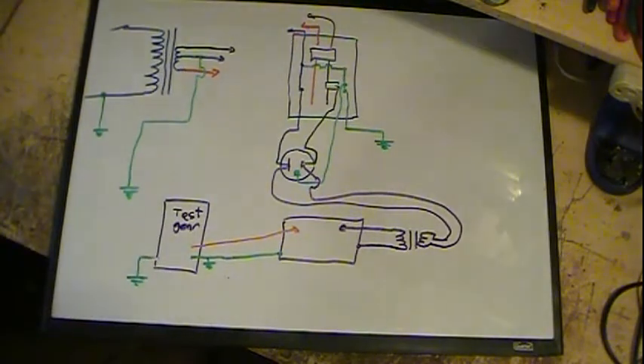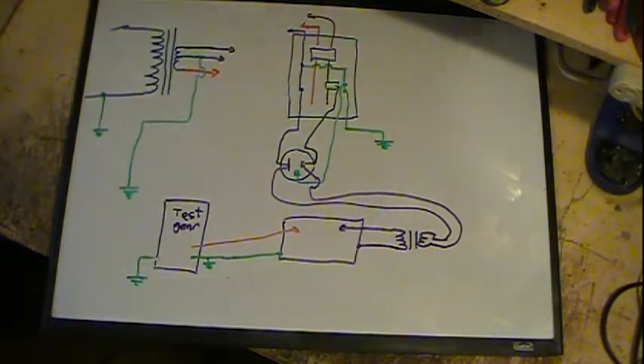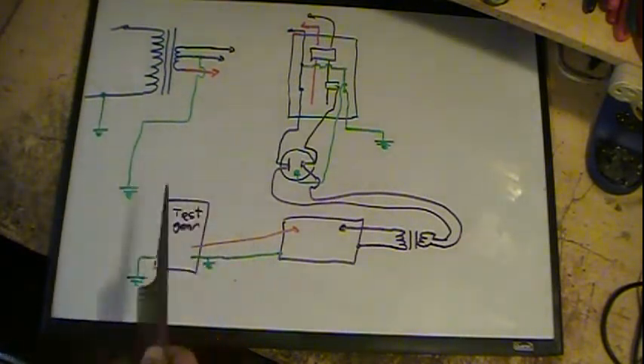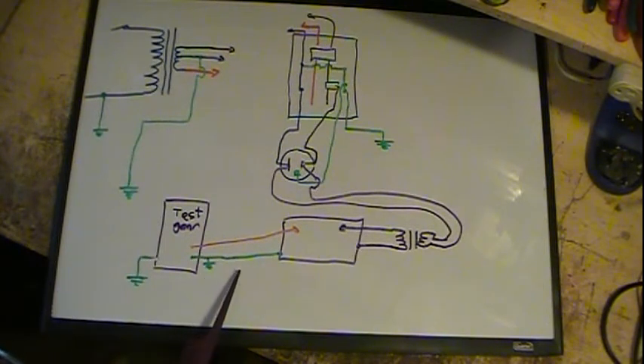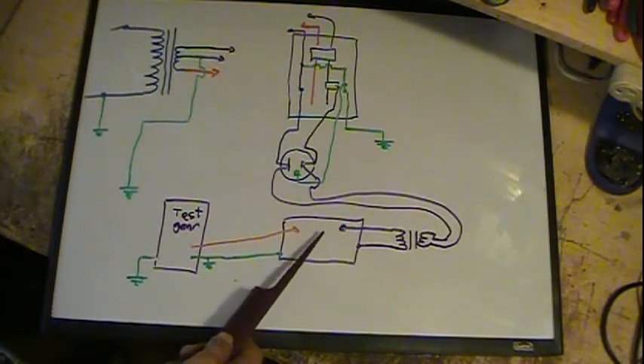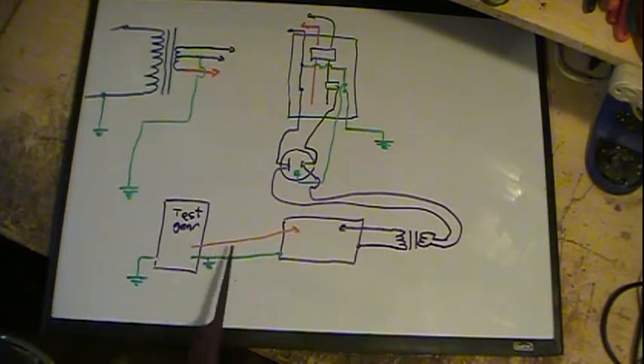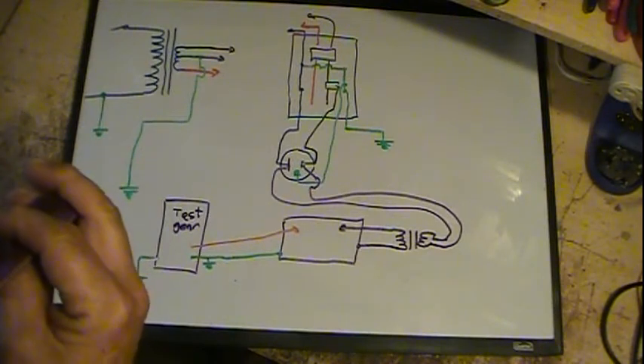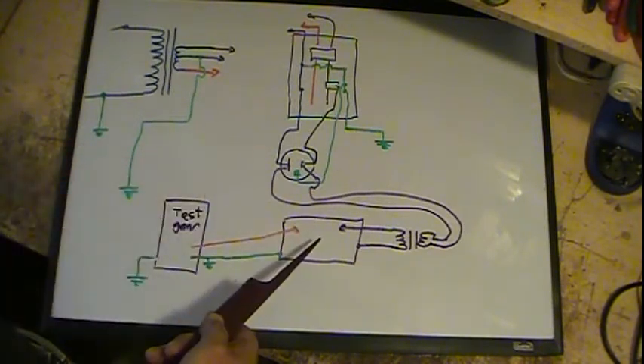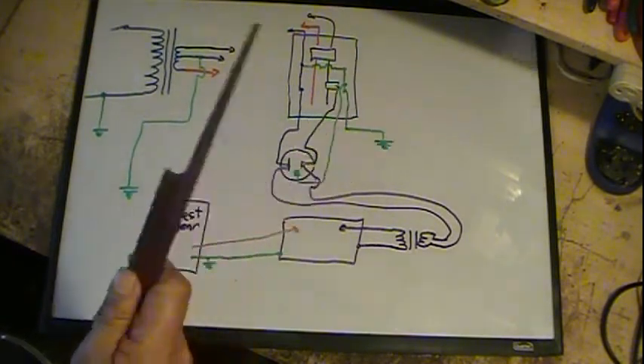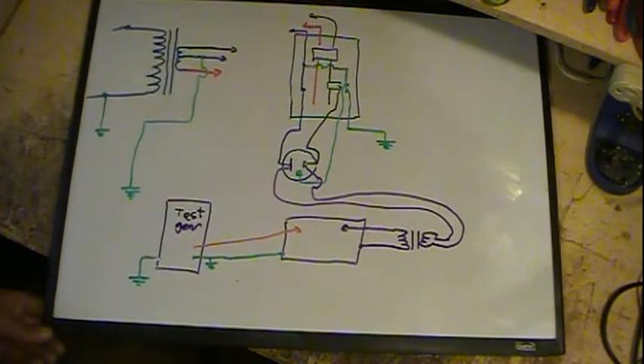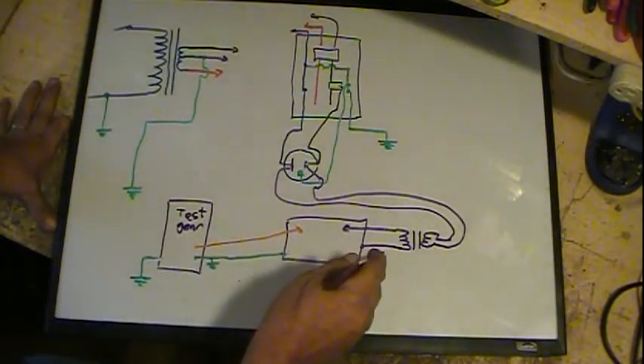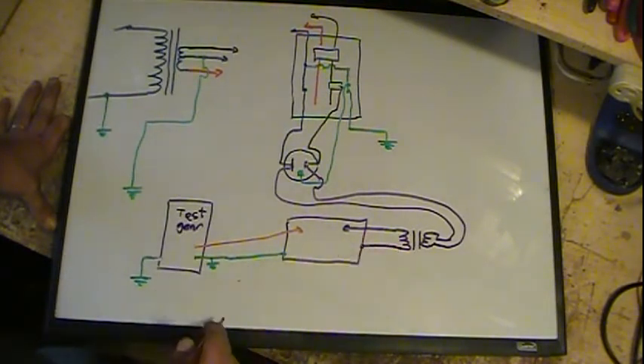Whenever you're working with something like this that doesn't have its own transformer power supply, use isolation, it protects your equipment. But there's a big but always in this. You got this guy hooked up, it's a scope or whatever, you got it grounded. Now you got to be careful, because the minute I hook that ground up for me as a human being, that chassis is not isolated anymore. Now I'm going to prove that point to you on this drawing. The minute I hook that up, I have grounded one side of this isolation transformer to earth.